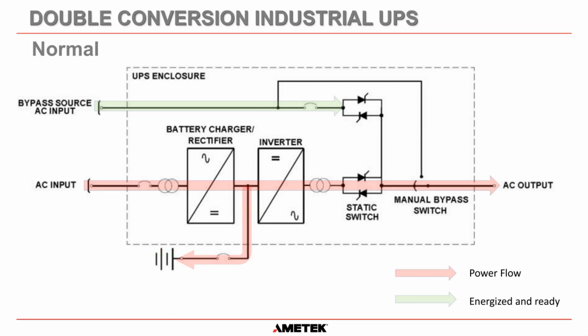Now, the connection between the battery and the rectifier and the inverter, they're all in parallel. So the DC bus not only feeds current to the battery, but it also feeds current into the inverter. And the inverter changes that DC back to AC. Then it goes through this isolation transformer, which has some filtering in it, and then you get a perfectly beautiful sine wave on the output there. And then here's the static switch that I mentioned earlier. That static switch will be on, so power will flow out through here to our AC output, which is your critical loads. Okay, so that is normal operation.